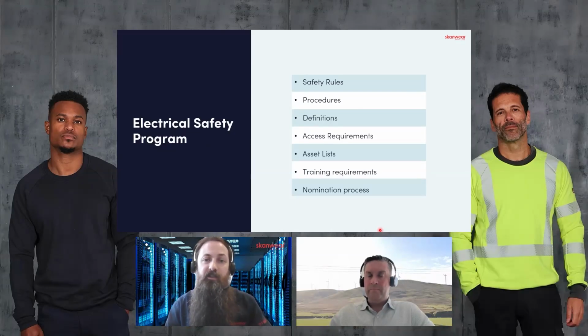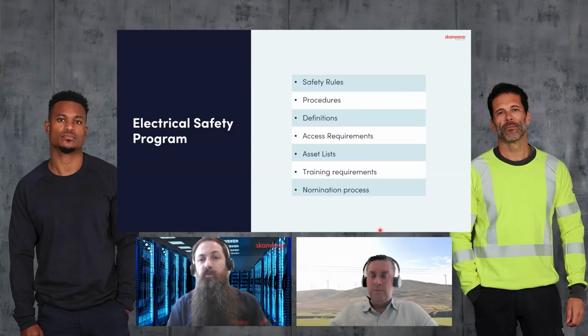The asset list part often gets overlooked in electrical safety programs, but this comes back to type of equipment, measures that you might take as an example. In the first video we watched, panning across an outdoor substation, if we had the asset list for that, we would know that both of those transformers had automatic tap changers, which operate automatically based on output of a nominal voltage that changes with load.